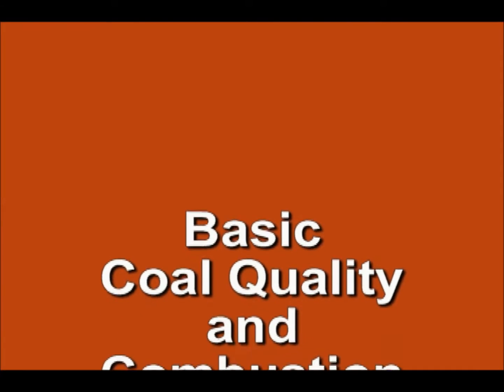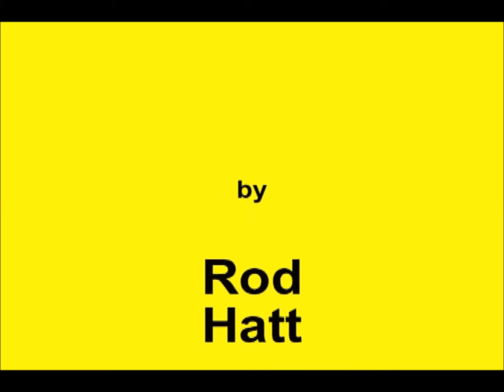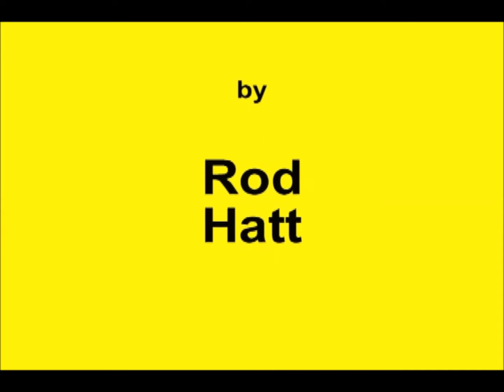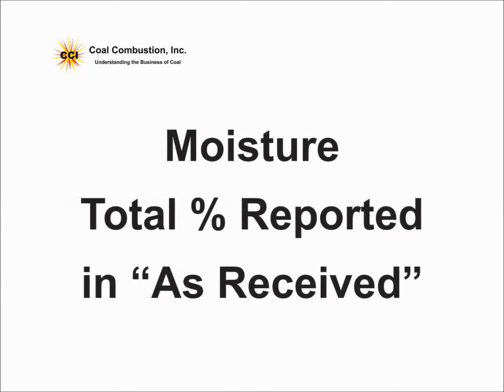Welcome to Coal Quality and Combustion Class. My name is Rod Hatt, and hopefully I'll help you understand coal a little bit better. Today we're going to talk about the proximate analysis, and particularly moisture. The moisture reported in the proximate analysis as received is the total moisture in coal, and it's important because it's a dilutant.